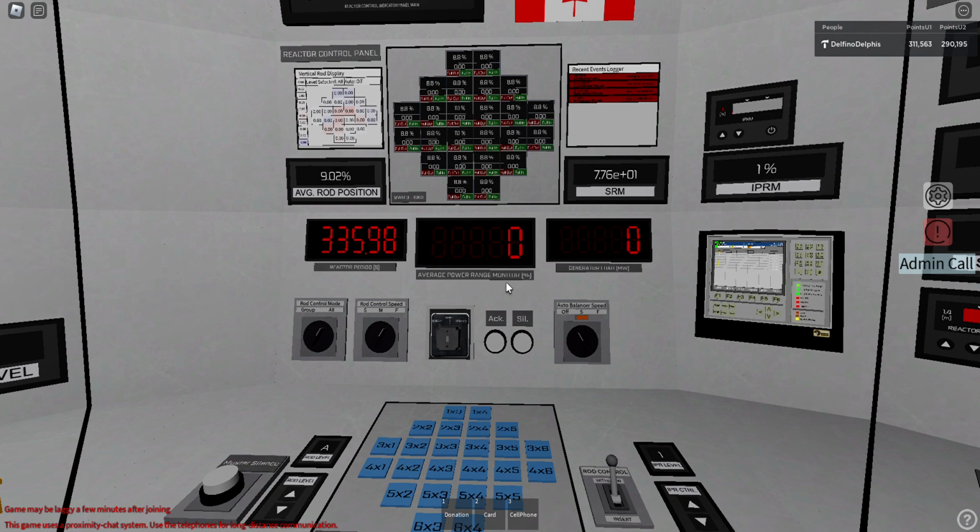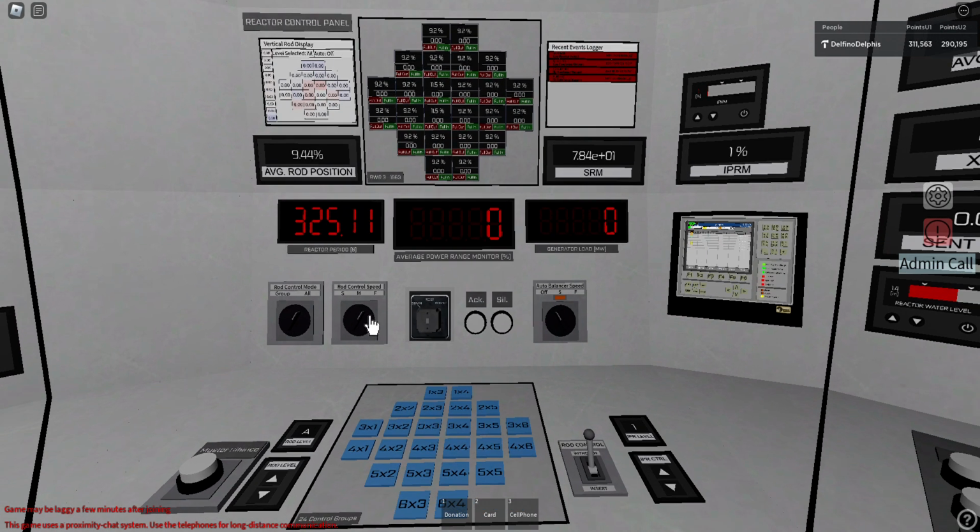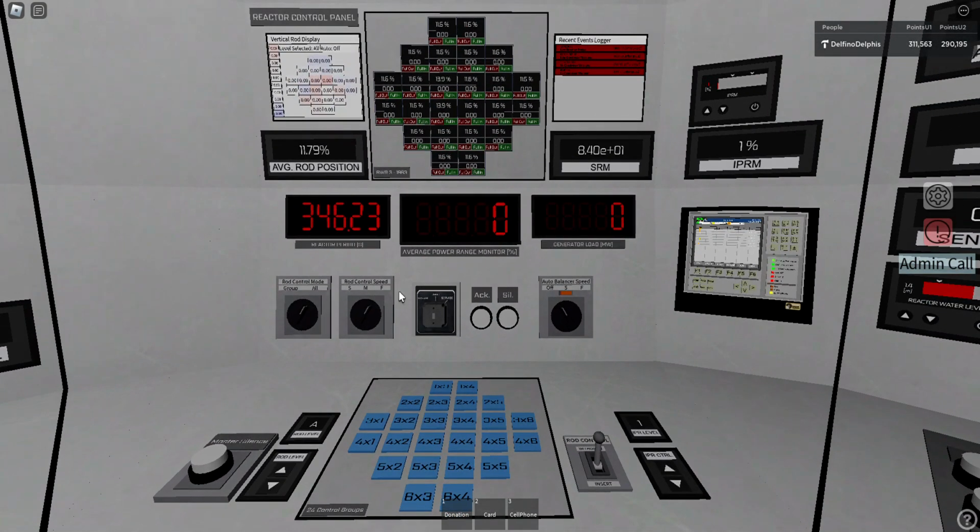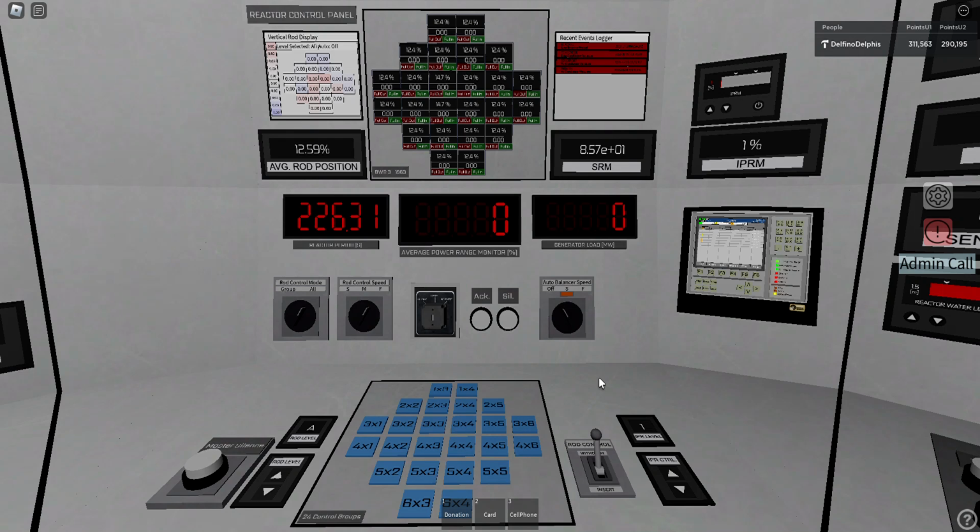Also, you need some experience to know how this works, because the reactor at some stage goes into so-called criticality, and it doesn't need any more rods to be pulled, and it will be rising in power despite that. So if I stop the rods now, it's not yet critical, because you can see the period is going to infinity. It will just stop at this power level. But at some later stage, if you even stop the rods, the reactor power will still continue to rise.